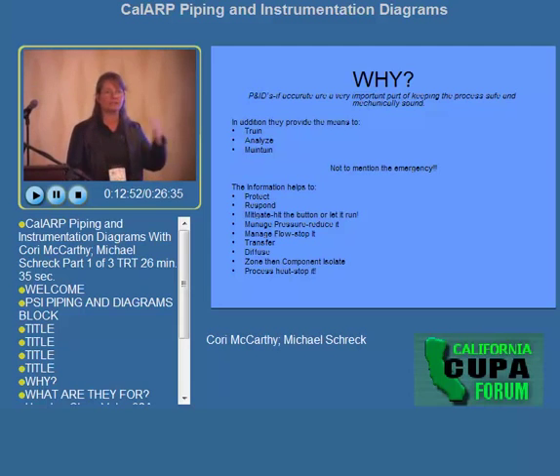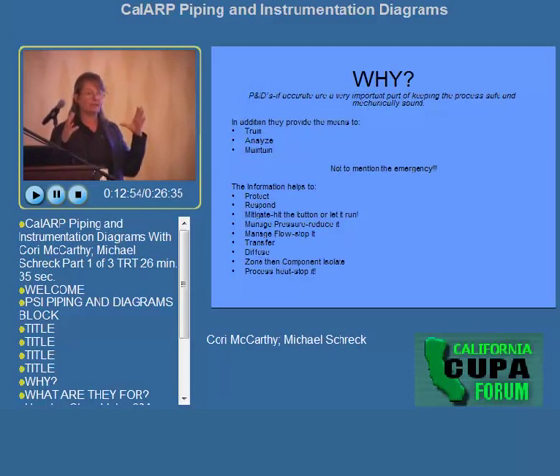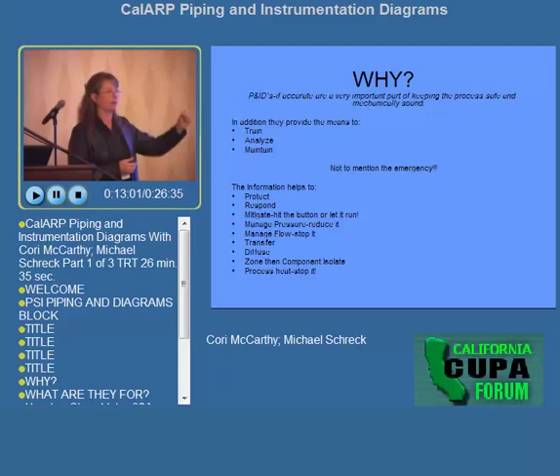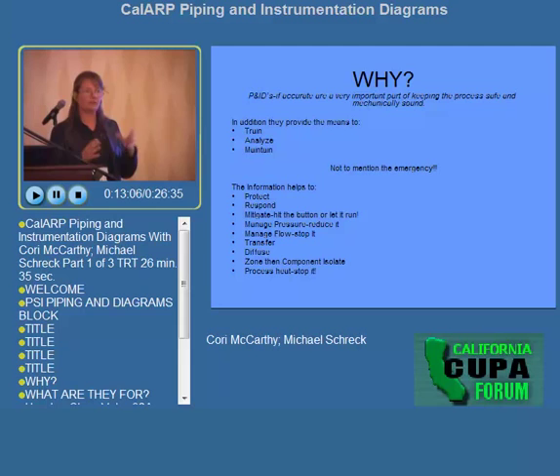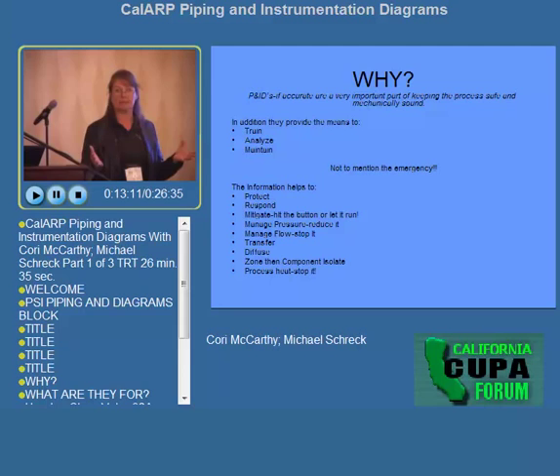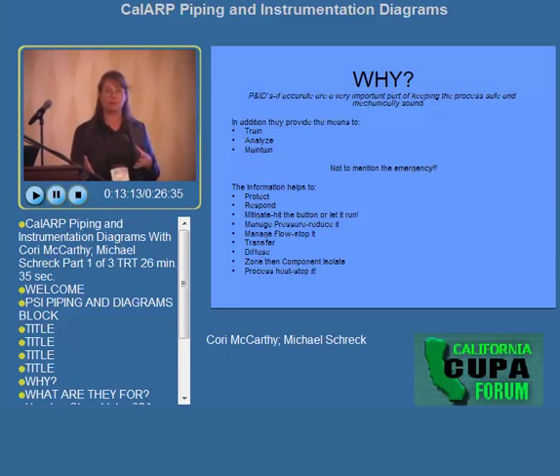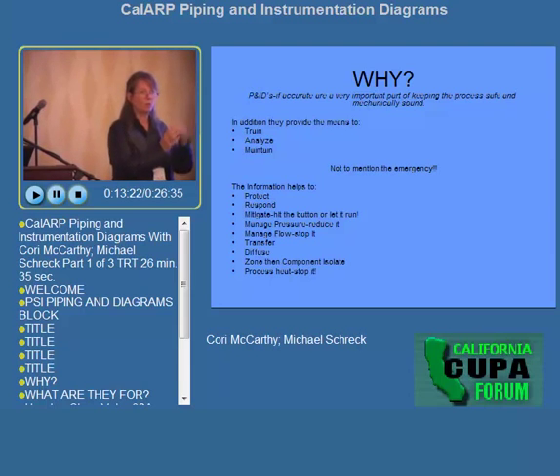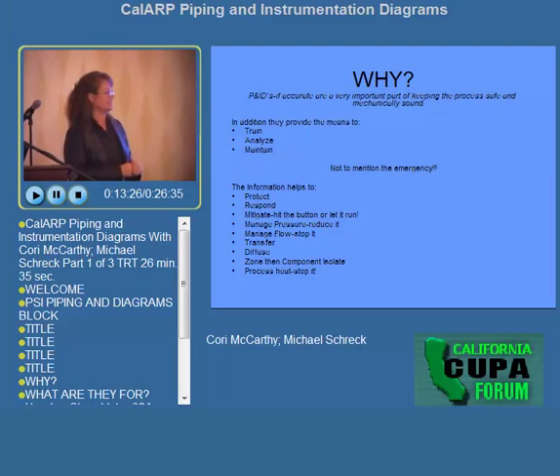We have pressure in our systems and we have the capability of managing that pressure to reduce the amount of what is released in a release scenario. We also need to manage the flow — can we close a valve from somewhere outside of the danger zone and stop the flow going to the hole in that pipe, that condenser, that evaporator? Can we transfer that ammonia using fireman's dump boxes and crossover valves?